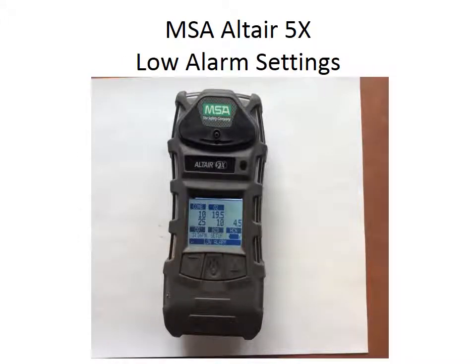So the meter is programmed with low alarm settings. These are factory settings that come with the meter, but we can alter these, but we've just chosen to leave them at the factory settings. So you can see for combustible gas, that top left one, COMB, we're looking at 10% LEL as the low alarm setting for the situations that we're going to be talking about here today, the combustible gas situations. And then you can just go through the rest of the sensors. O2 at 19.5%, carbon monoxide, the low alarm starts at 25 parts per million, hydrogen sulfide is 10 parts per million, hydrogen cyanide is 4.5 parts per million.